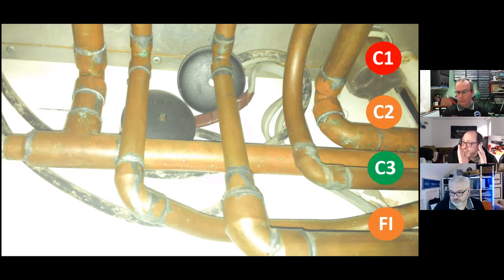So is there risk of vibration? Is there free movement of the joint boxes? The joint boxes aren't fixed, clearly. So the utilization of this cupboard space, maybe for clothing, whatever, would result in vibration that would result in mechanical movement. That's going to, over time, potentially create further danger, and I'd want that out. Do you know what? You're right. I would probably agree with you here, actually, and go C2.